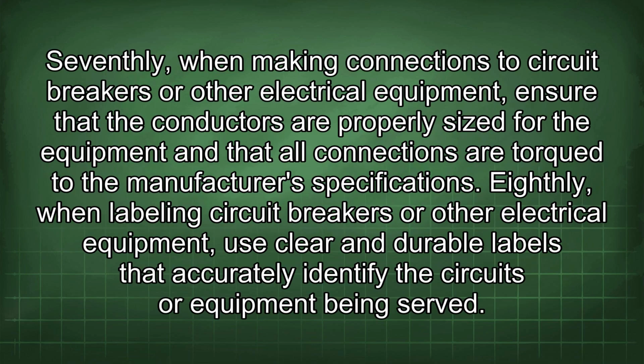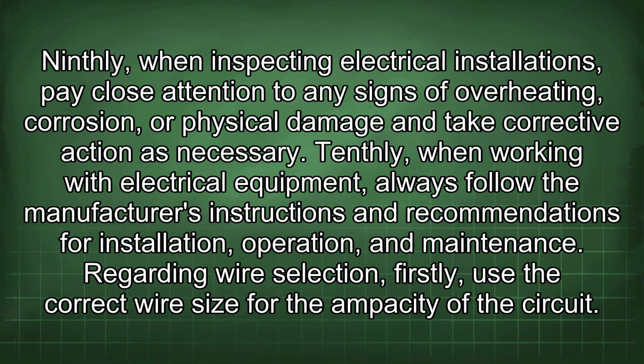Seventhly, when making connections to circuit breakers or other electrical equipment, ensure that the conductors are properly sized for the equipment and that all connections are torqued to the manufacturer's specifications. Eighthly, when labeling circuit breakers or other electrical equipment, use clear and durable labels that accurately identify the circuits or equipment being served. Ninthly, when inspecting electrical installations, pay close attention to any signs of overheating, corrosion, or physical damage and take corrective action as necessary. Tenthly, when working with electrical equipment, always follow the manufacturer's instructions and recommendations for installation, operation, and maintenance.